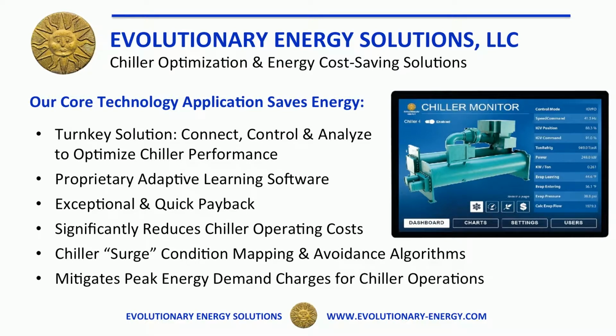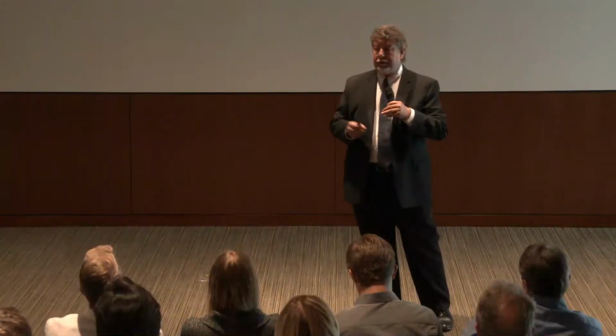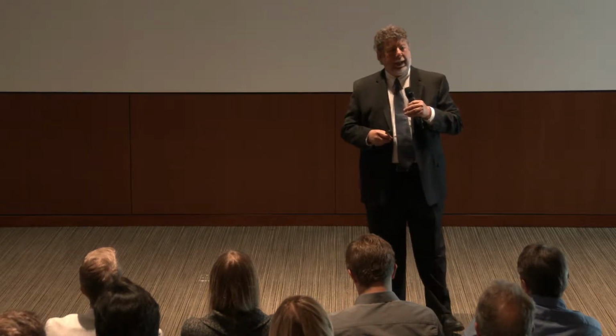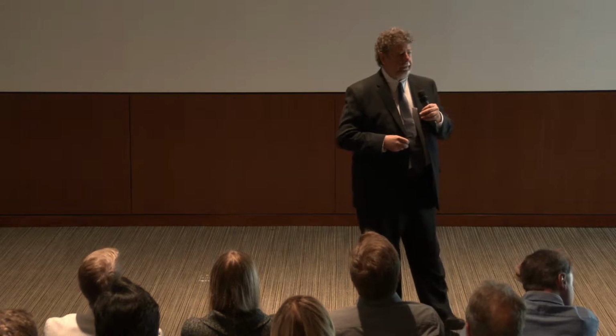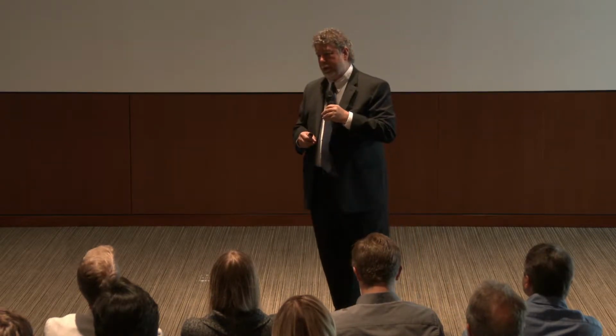What we've been able to do is go in where there are large industrial chillers, the biggest, most onerous industrial size for gigantic buildings. In a retrofit situation, dealing with buildings that are 20 or 30 years old with very inefficient chiller systems, we retrofit them, saving an extraordinary amount of energy by adapting them with what we call an interface system, which overrides what the original equipment manufacturers have in place.